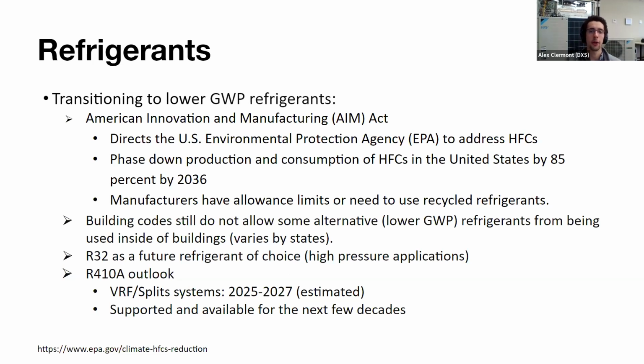Now, this is where the American Innovation and Manufacturing Act, the AIM Act, was passed in 2020 as part of a COVID relief bill. Under this act, it gave the EPA the authority to phase down HFCs. It advised the EPA that the production and consumption of HFCs should be reduced by 85% by 2036, which gets us in line with the international phase down plan called the Kigali Amendment.